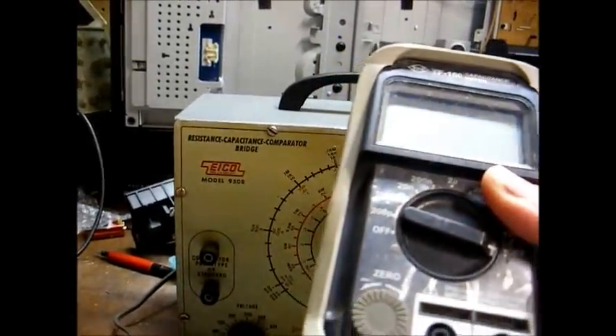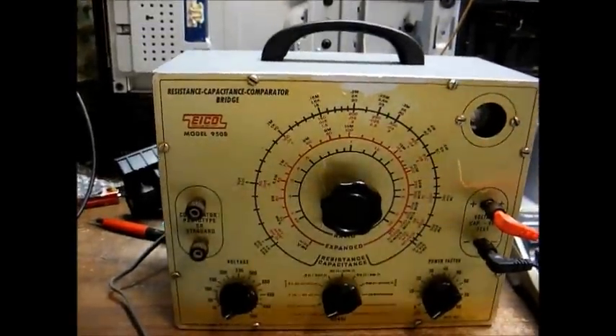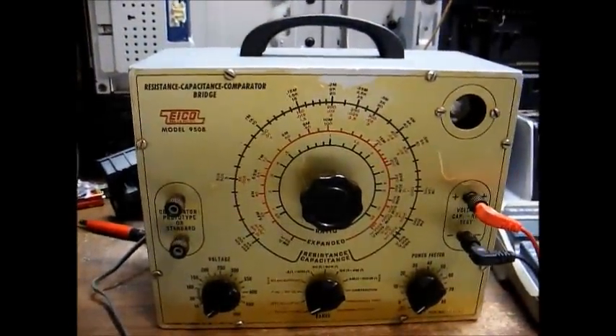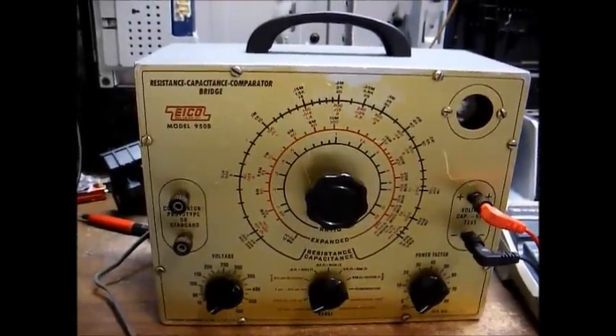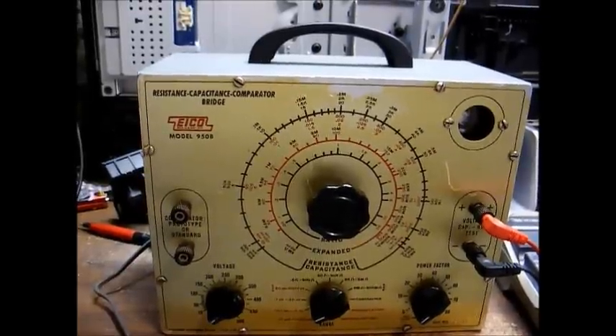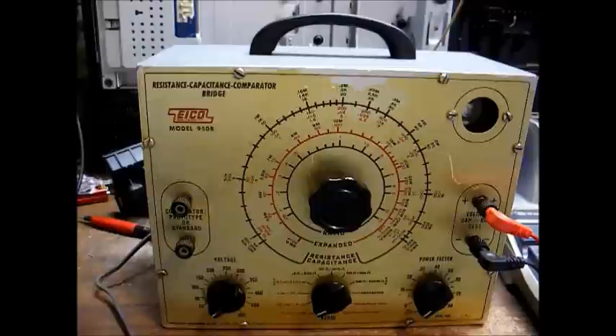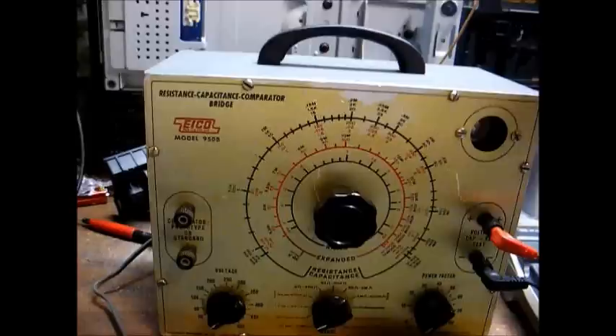the amount of voltage applied across the capacitor is very small. Therefore, a capacitor might actually check OK. But when that same capacitor is operated in circuit where several hundred volts is placed on it, then the capacitor might exhibit leakage. And that's where this tester comes in.